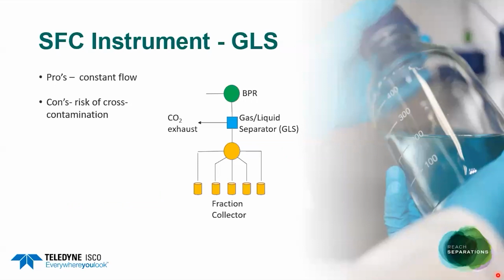Okay, the second option is to have a single GLS pre-fraction valve. Now the advantage with the design is you get flow constantly running through your gas-liquid separator, and this almost acts like self-cleaning. However, on a downside to this is you could get risk of cross-contamination of the fractions you've worked hard to separate, and that all depends on the design of the liquid separator.